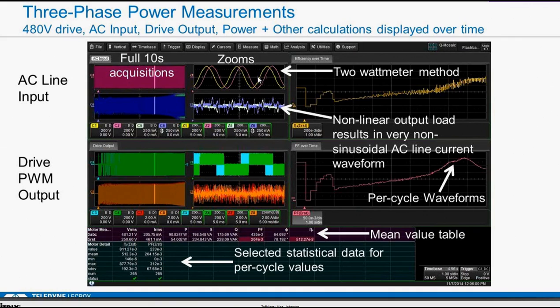I can see my waveforms right here. I can see they're fairly sinusoidal, as we described. Note that the current on the line side is not sinusoidal at all. And that's because the load is a very nonlinear load. So it draws current in a very nonlinear way.